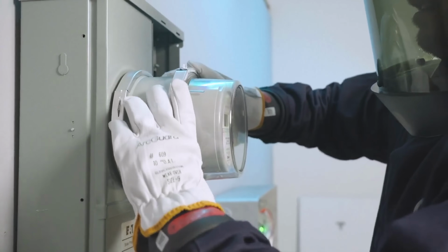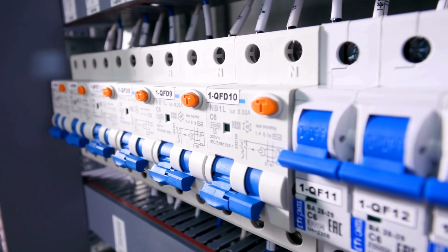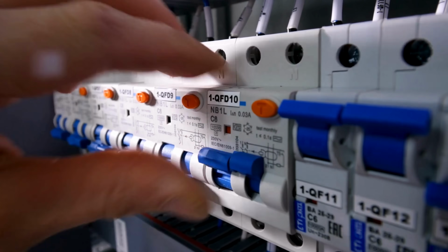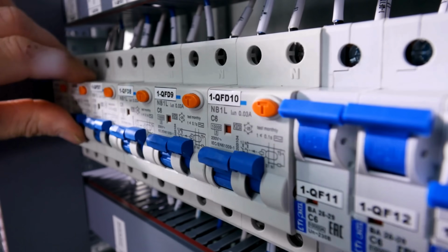Tesla came up with an innovative new way to do this, where there's an adapter that fits around your electric meter that does the disconnecting from the grid based on a signal it receives from the inverter. The advantage is that as an installer you don't really have to worry about modifying the inside house wiring to complete a battery backup install. All of that switching can be done right at the meter base, so as a contractor you don't take on any risk of modifying the in-house wiring, and as a homeowner you don't have the disruption of the contractor cutting up your drywall or pulling circuits in and out of your electrical panel. That entire switching can be done right there at the meter base.